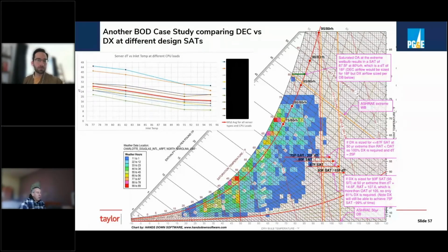If we raised it all the way up to a 93 degree supply temperature, we'd have a low delta T, 15 degrees, but we could actually get away with partial DX. In this case, I think it was 81%. So we could cut out 19% of our DX capacity because our return air temperature was actually going to be above the worst case ambient temperature. So we would always be on economizer, even on the 50-year extreme hottest day.